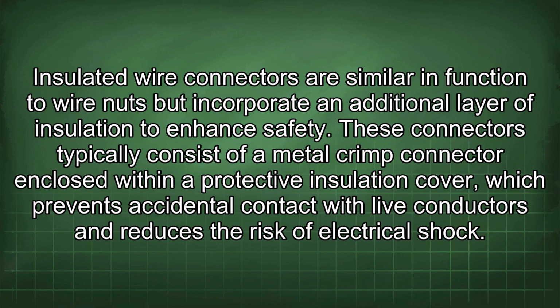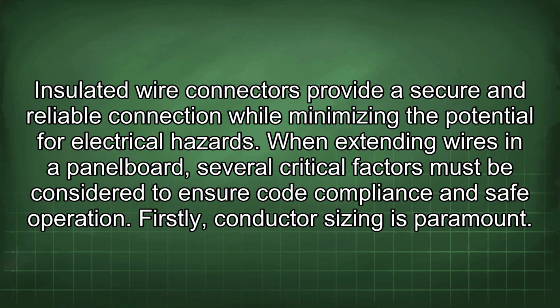These connectors typically consist of a metal crimp connector enclosed within a protective insulation cover, which prevents accidental contact with live conductors and reduces the risk of electrical shock. Insulated wire connectors provide a secure and reliable connection while minimizing the potential for electrical hazards. When extending wires in the panel board, several critical factors must be considered to ensure code compliance and safe operation.